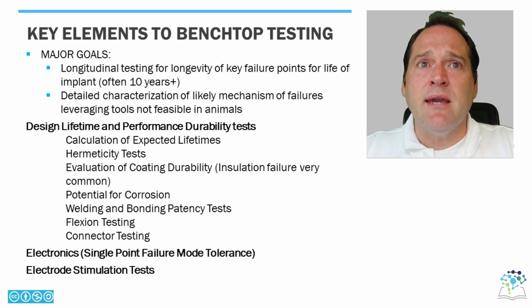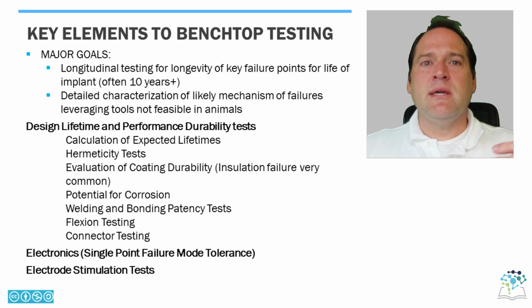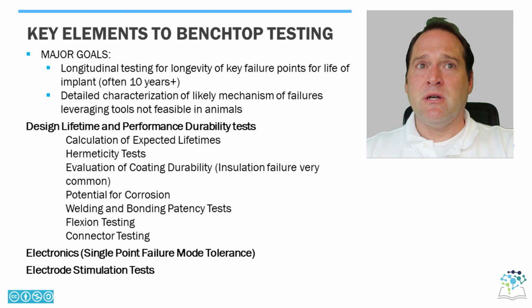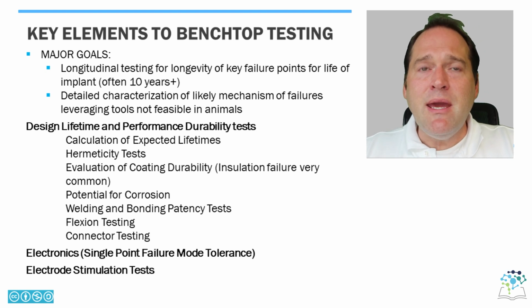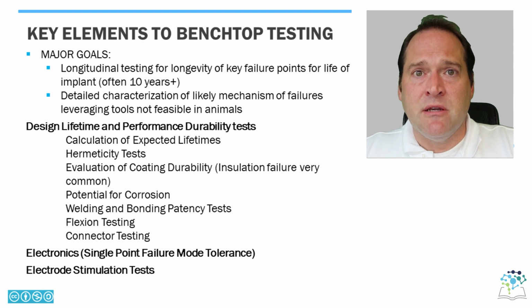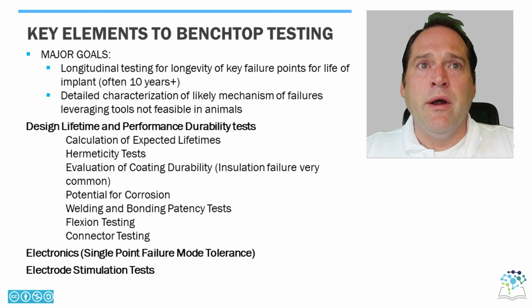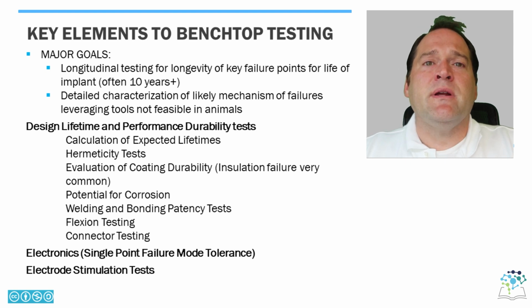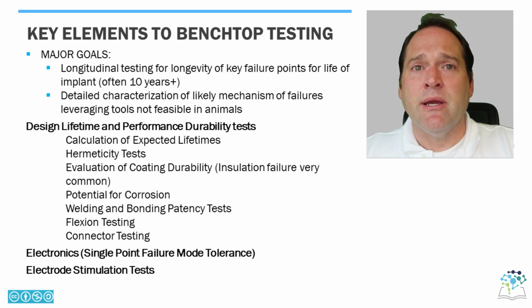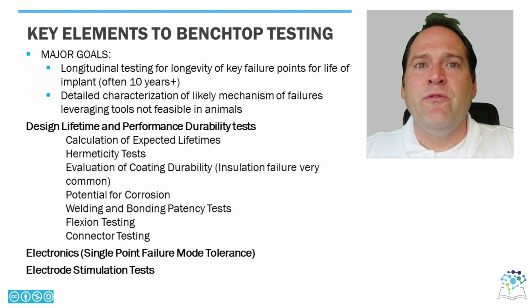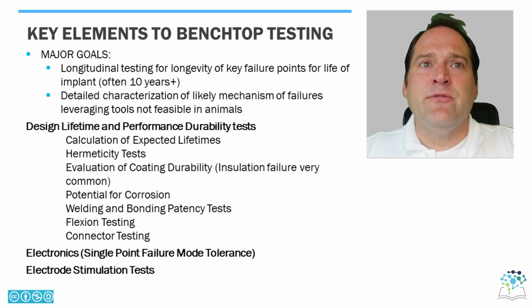So if you look at these guidances, there's really several key tests that are part of the benchtop testing plan. The major goal of the benchtop testing plan, as stated earlier, is, one, longitudinal testing for longevity of key failure points for the life of the implant. You're only going to implant in the animals for 3 to 6 months, and so you're really trying to extrapolate where these devices will fail, or if they'll fail, when they're implanted for 10 years.